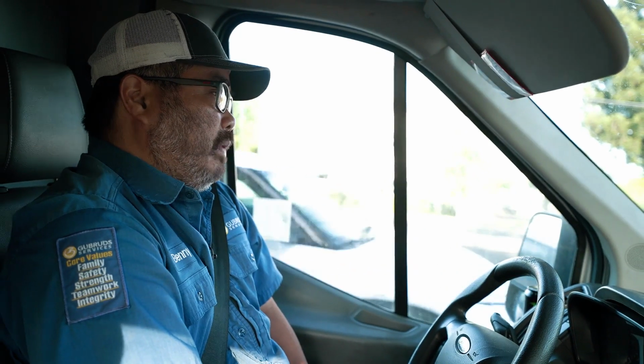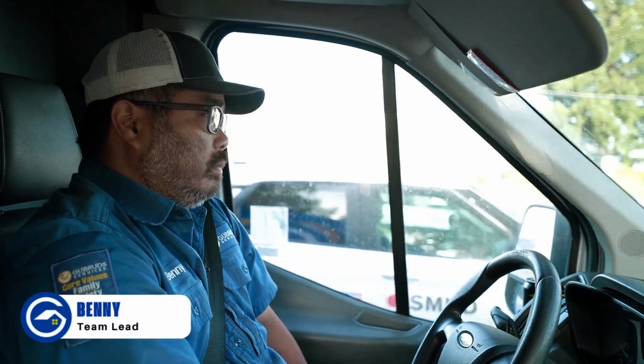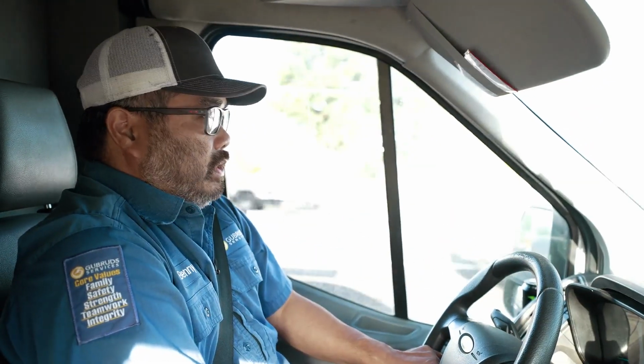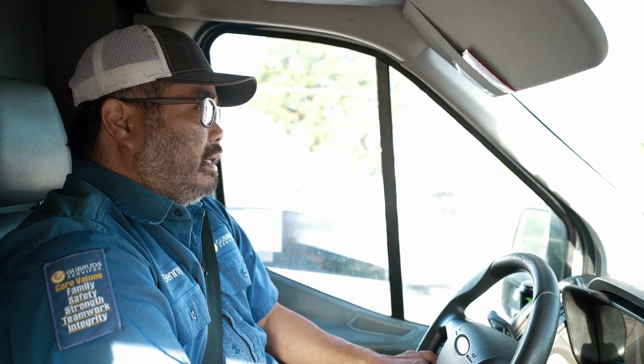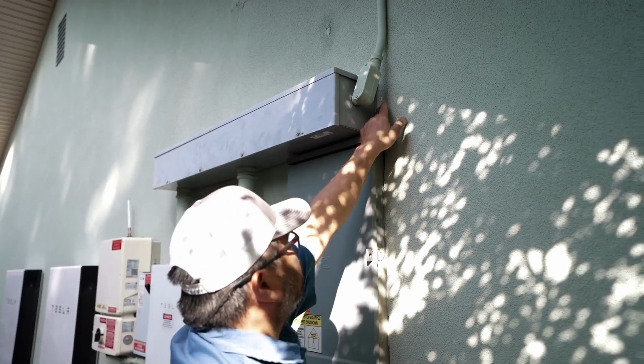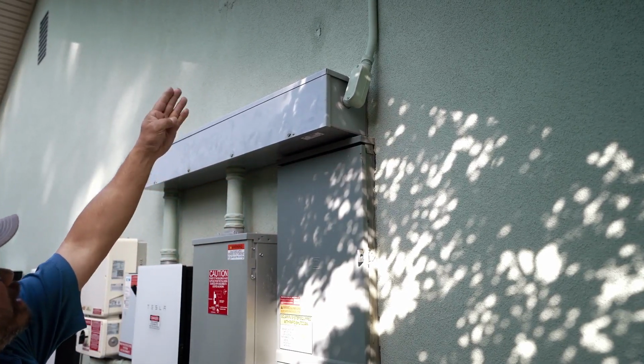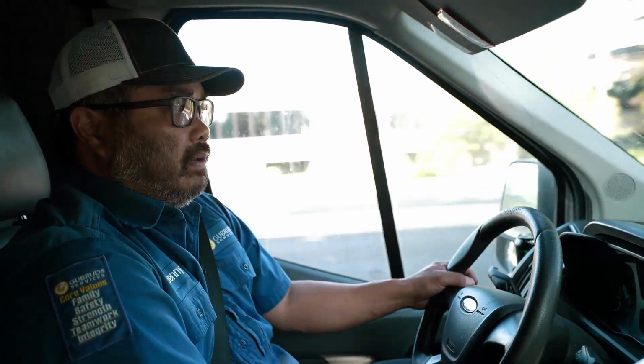So I started taking pictures of everything inside the gutter. I took thermal readings inside the gutter, all that stuff too. And I showed him the pictures on the tablet. It was very transparent. I was like, hey, you've got a bigger issue here than just replacing the wires from aluminum to copper. You have water getting into this, and it's rusting up everything. Literally, the gutter looked like it's been there forever, but it's only been there for a couple of years.